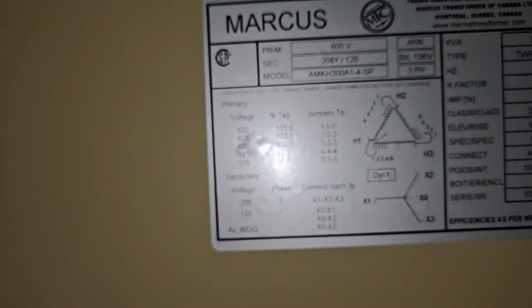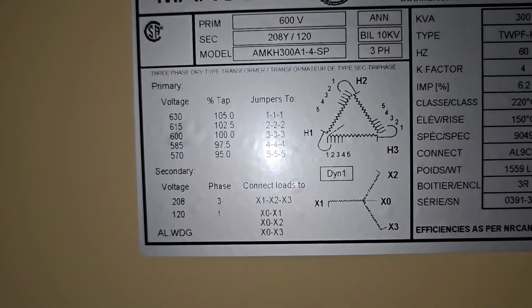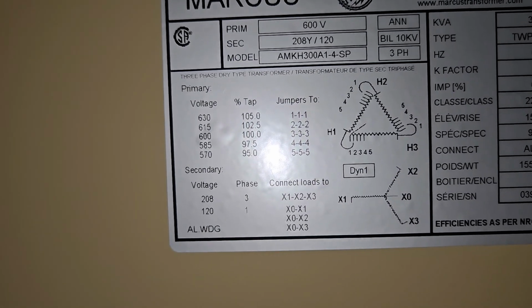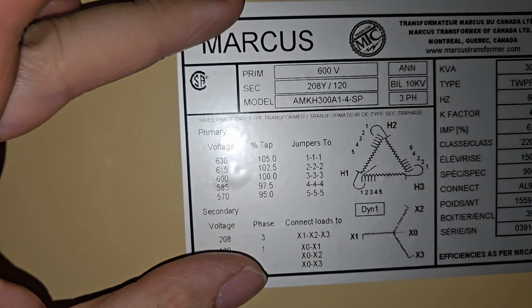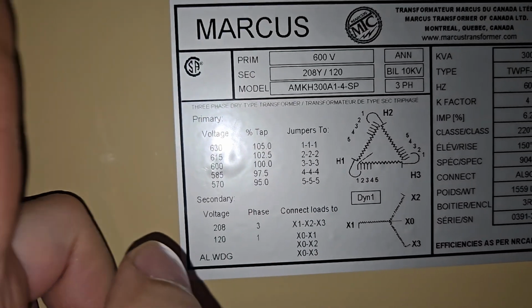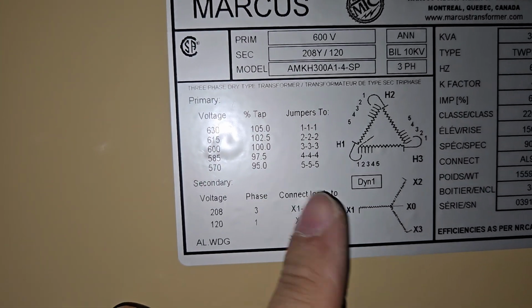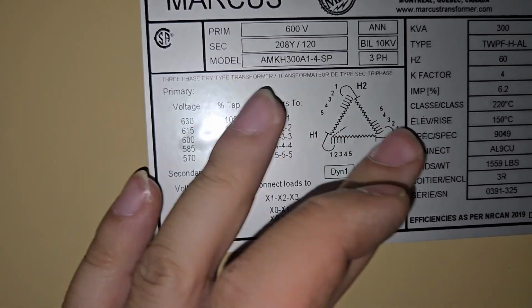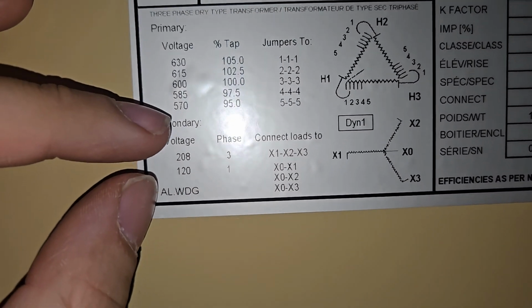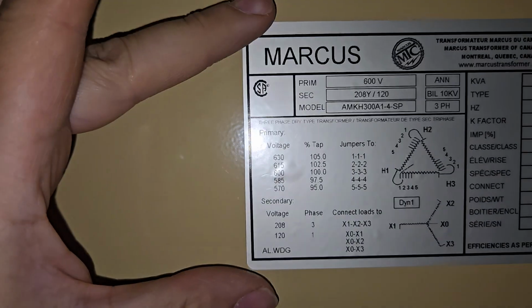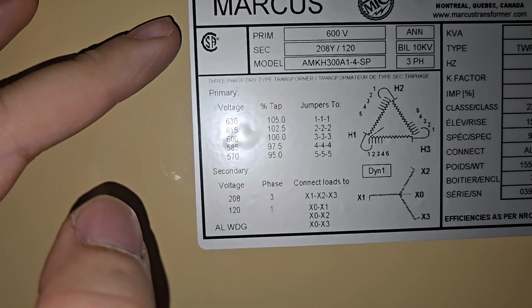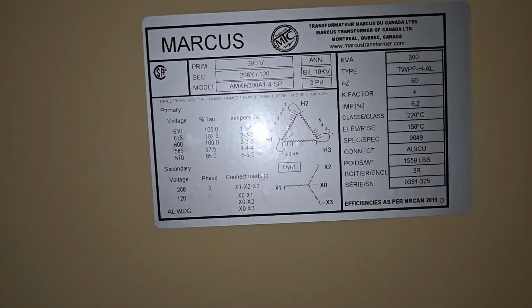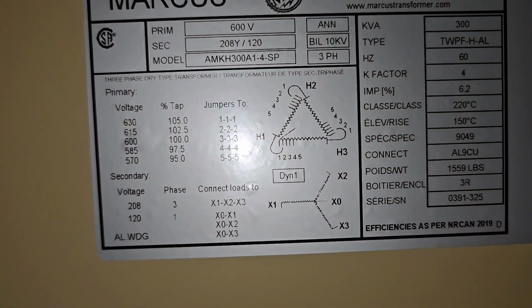Now it's not like a computer or anything. All this really is, is a big coil of wires inside, and by tapping it, we're lengthening the coil or shortening the coil. So on one side you got a big coil and on the other side a small coil, and as the power goes through one coil, it creates a magnetic field, and the magnetic field creates current in the other coil, which gives us our output. And the ratio of coil sizes changes the voltage. So if on this side I got wire wrapped around 600 times, and on this side I got a wire wrapped around 208 times, then I get my voltage difference. That makes sense. So now we do that for three phases, and that's how we end up with a transformer.